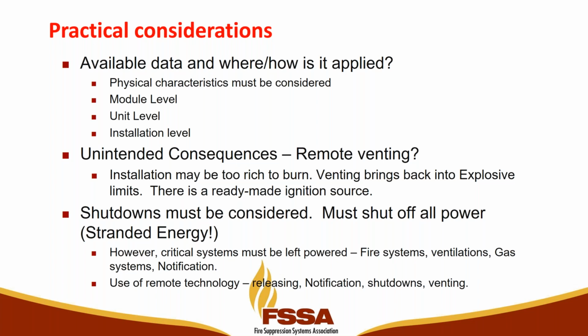Then shutdowns: how do we turn off power? Because ultimately, code doesn't really address this for an event that could go on for 4 hours, 5 hours, 2 days, because they can reignite. So what do we do for battery backup, not only on our systems, but on the BMS systems as well? It's kind of ironic having battery backup on a battery system, but ultimately you've got to figure that a 5-minute alarm is not going to give you enough safety if we've got a high gas level event. So we've got to be looking at what options may come up into the world on making sure that first responders are safe and have information.